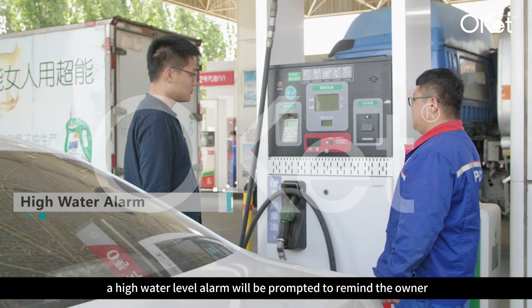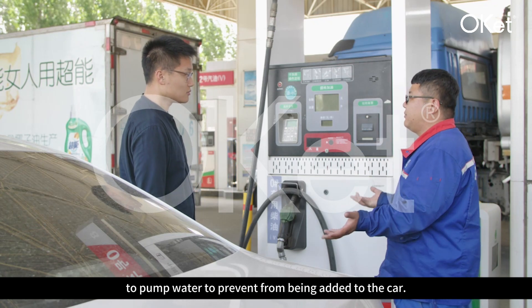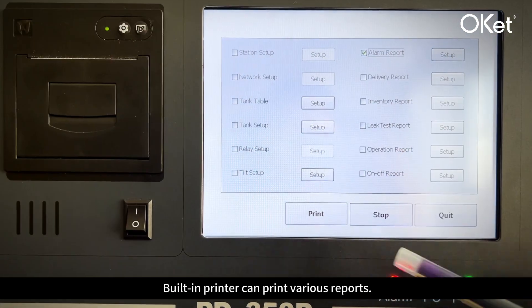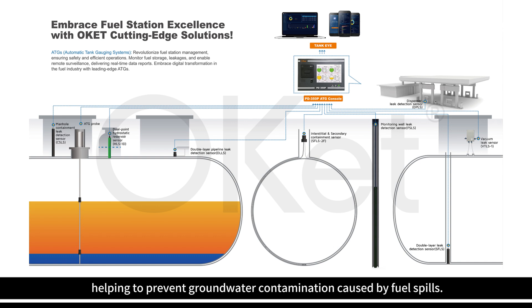When the water level is high, a high water level alarm will be prompted to remind the owner to pump water, preventing it from being added to vehicles. The built-in printer can print various reports. Additionally, the ATG system can directly connect to integrated leak detection sensors, enabling unified real-time monitoring and alarm notifications for fuel station leaks.